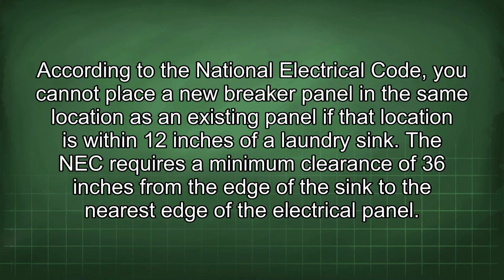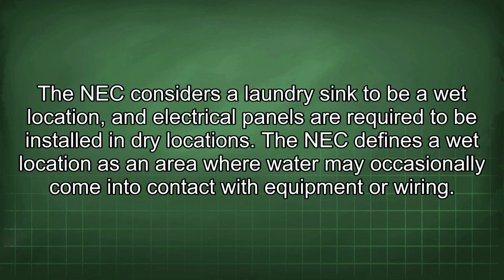According to the National Electrical Code, you cannot place a new breaker panel in the same location as an existing panel if that location is within 12 inches of a laundry sink. The NEC requires a minimum clearance of 36 inches from the edge of the sink to the nearest edge of the electrical panel. The NEC considers a laundry sink to be a wet location, and electrical panels are required to be installed in dry locations.